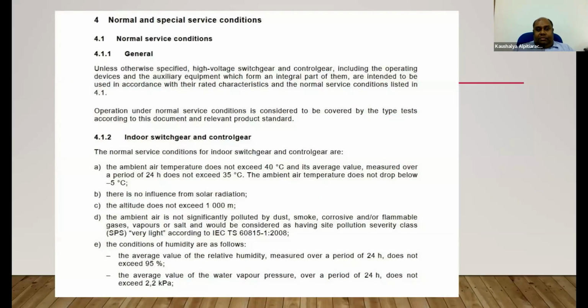Yes, service conditions. It says the temperature does not exceed 40 degrees, the average does not exceed 35 degrees over a period of 24 hours, and it does not drop below minus 5 degrees. No influence of solar radiation. Altitude limitation not exceeding 1000 meters. And if the ambient air is not significantly polluted, yes, you can refer to 60815, what we referred to in earlier cases. And the humidity shall not be greater than 95% over a period of 24 hours, and the average pressure over 24 hours shall not exceed 2.2 kilopascal.